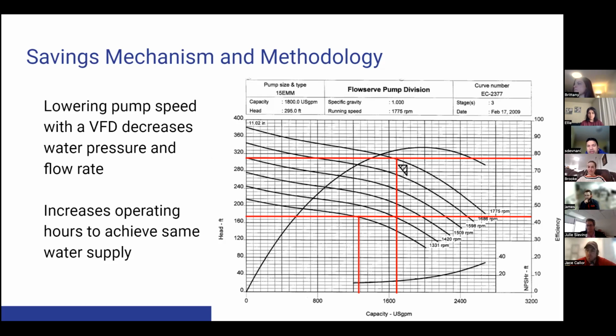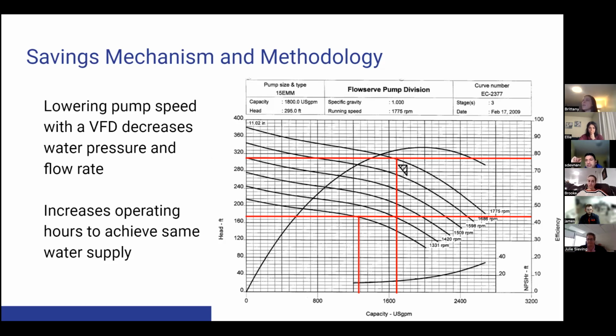So you have to remember, if this cooling tower were, say, on the top of a 200 feet high office building downtown, and the pump's at the basement, then even though you could trim the impeller down to 160, let's say, when you get to 160, that water is not going to get to 200 feet high. That's just vertical head that it has to overcome. Now, if the cooling tower and the pump are both on slab at the same grade, you avoided that. You just need to have NPSH so that your pump doesn't cavitate. But keep in mind that when you're dealing with cooling towers, you are moving water at elevation. You're moving water up a vertical open column. That's just lift. And you have to make sure that your pump head doesn't get too low. Okay? Clear? Cautioned enough?